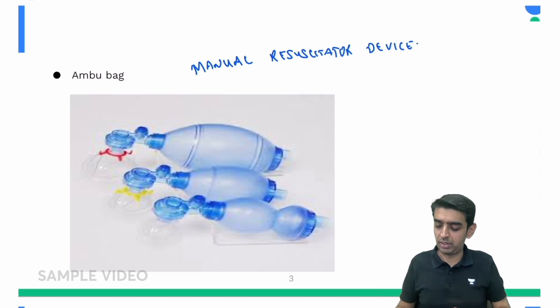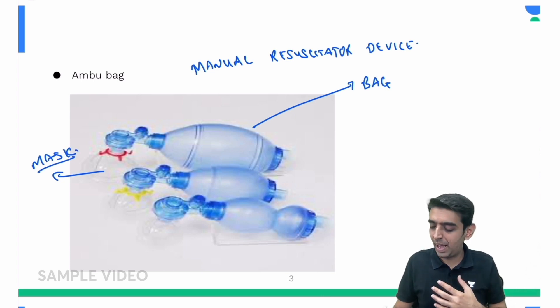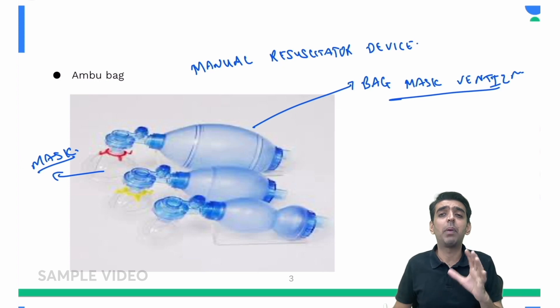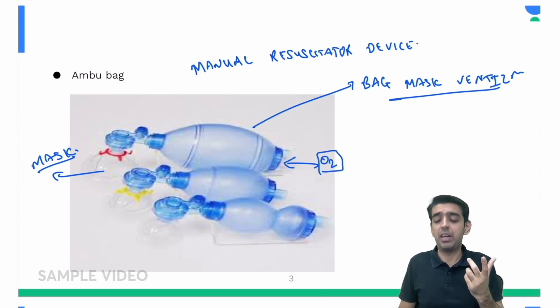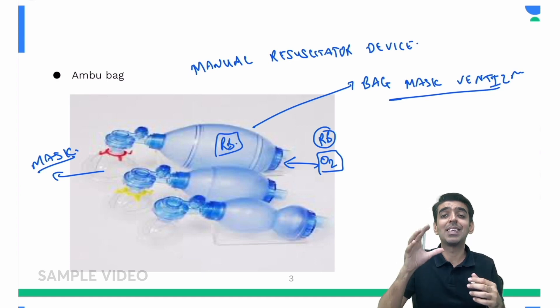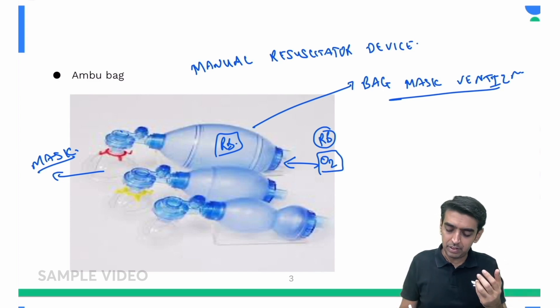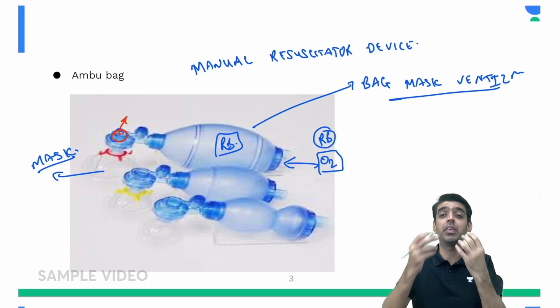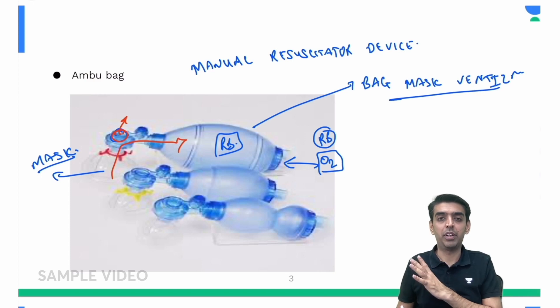As you can see, the manual resuscitator consists of a bag with a mask fitted on it, and it is also used for bag mask ventilation. From one end you can attach the oxygen tubing and reservoir bag. It is a self-inflating bag — once you press and release it, it inflates on its own. It also has a unidirectional valve, also known as the fish mouth valve or Ruben's valve, so expired air goes directly back to the atmosphere and does not return to the reservoir bag.